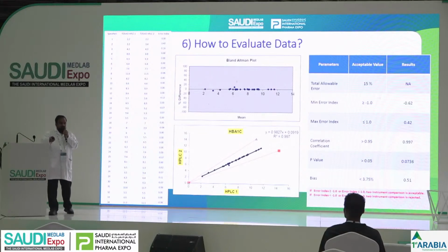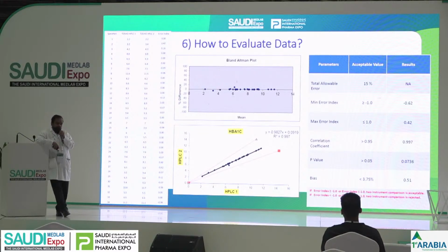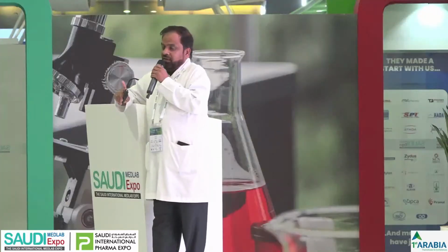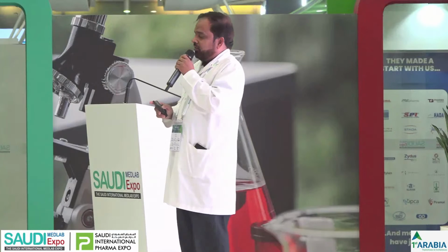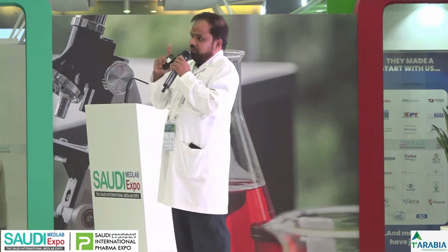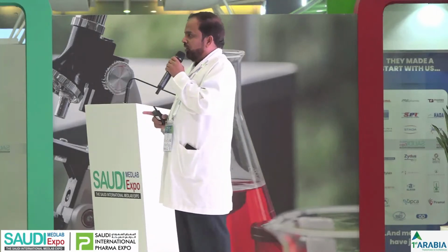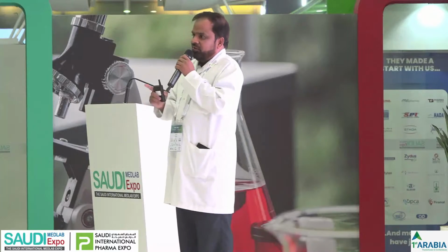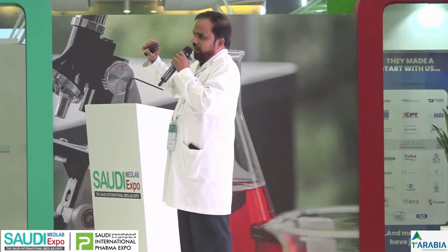Normally, as mentioned previously, the correlation coefficient is 0.95 or greater. But the correlation coefficient is not the indicator of a good method comparison. The minimum and maximum error index should be within the limit, minus 1 to plus 1.